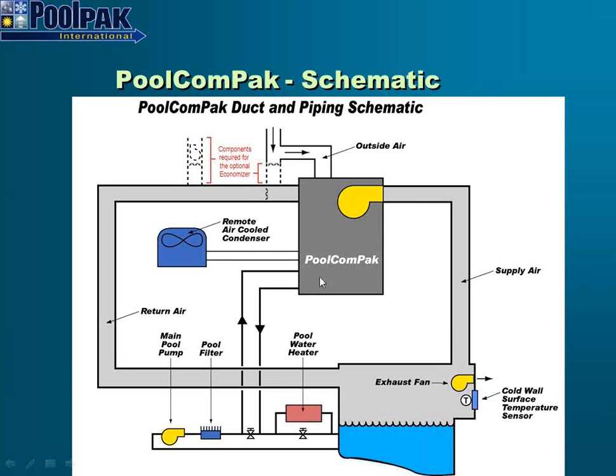PoolComPak units do not have integral exhaust fans, so to maintain proper ventilation levels, a dedicated exhaust fan is required. Another standard feature of the PoolComPak and all PoolPak units is a cold surface temperature sensor. This is how we control PoolPak units.